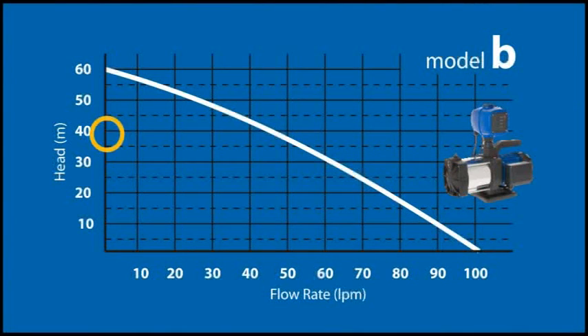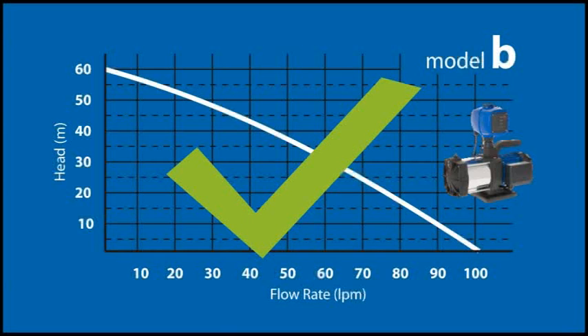Let's try the pump curve for model B. Again, find 39 metres on the head or vertical axis, and run an imaginary line across the graph till you meet the pump curve. Then draw a line straight down to the flow rates. Is this pump able to produce the flow rate required at the pressure you require? In the case of model B, the answer is yes. This means model B has both the pressure and flow rate to meet Aunty Flo's needs.